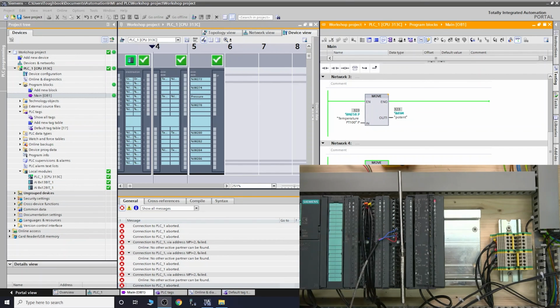By testing the card properly, I found out that my resistor gives you a sort of good idea as well if you are having a fault with your system and readings are not matching or something's jumping around and not functioning correctly. Your best way, because remember, this card doesn't have diagnostics, it will not be popping out anything to you and not showing you anything. So it's a very good idea to have a handy TIA Portal next to you, connecting to it, and have a look what's going on.